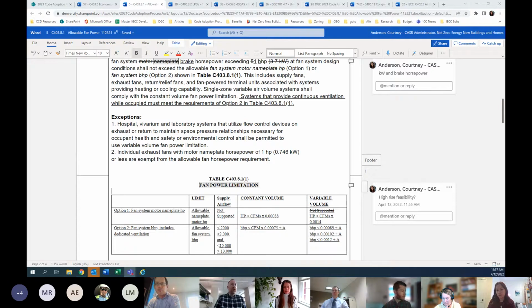My only concern is that typically equipment replacement or small remodels in existing buildings use the prescriptive path, and the existing portion of our code requires compliance with section C403, which encompasses this—so they'd be required to meet it. I agree that if there's a new system with all new ductwork, they should be able to meet this. But if it's an existing system where they're just pulling one piece of equipment and dropping in a new one, with no ductwork changes, that could be a challenge.